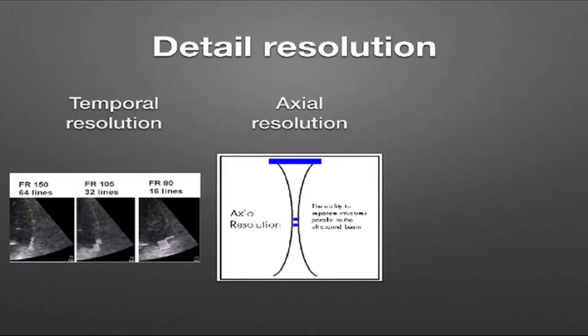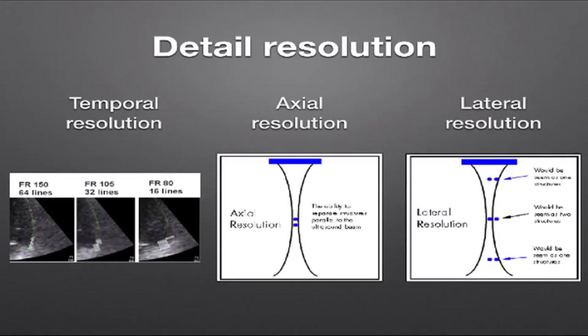To summarise detail resolution: temporal resolution relates to frame rate — the greater the frame rate, the better the ability to image a moving structure, and differences between 40 and 80 frames per second become apparent when slowing down and making measurements. Axial resolution is the ability to separate structures along the direction of ultrasound travel. Lateral resolution is the ability to separate two structures on the plane perpendicular to the direction of ultrasound travel.